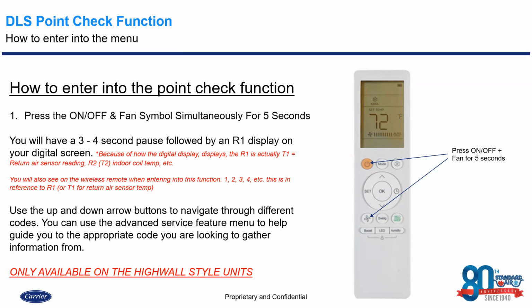We're going to go ahead and press the on and off button and fan button simultaneously and hold them in for 5 seconds. Okay. What you're going to see pop up after that 5 seconds is going to be a number 1. From there, you can adjust using your up arrow and down arrow to 1, 2, 3, and 4. What that is essentially in reference to is T1, return air sensor. Number 2 is T2 for indoor coil temperature. T3 for outdoor air temperature, okay, depending on the situation. Excuse me, T3 is actually outdoor coil temperature. T4 is outdoor air temperature.